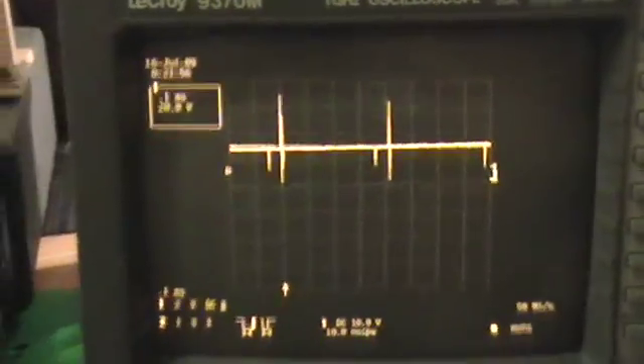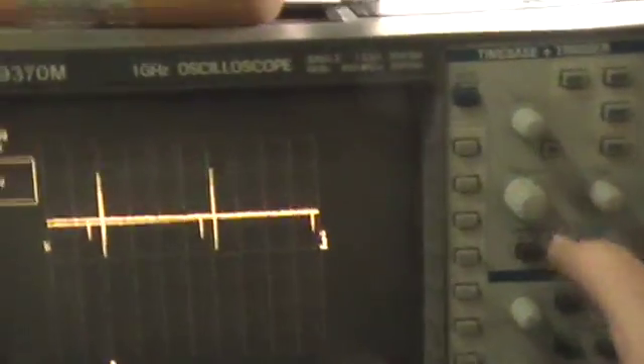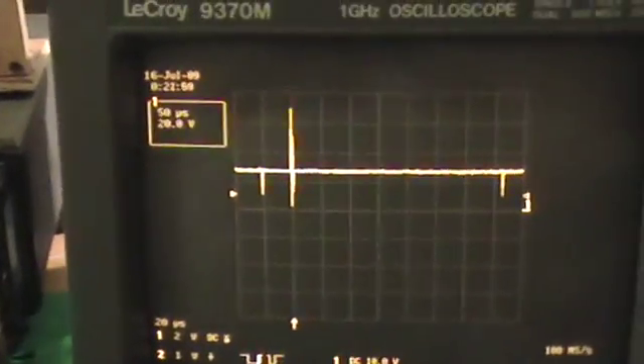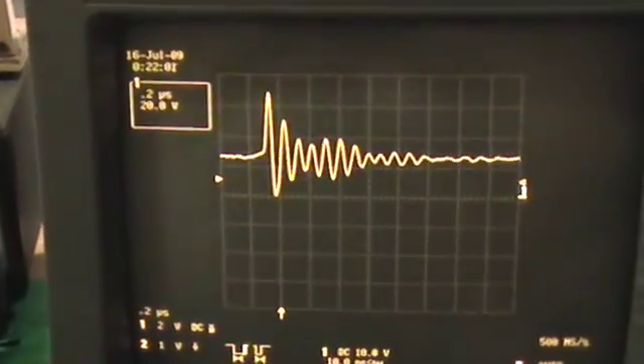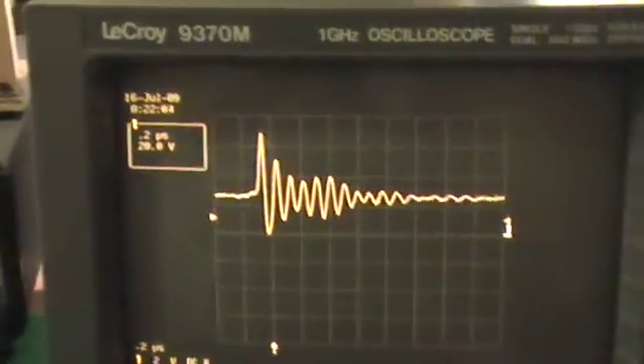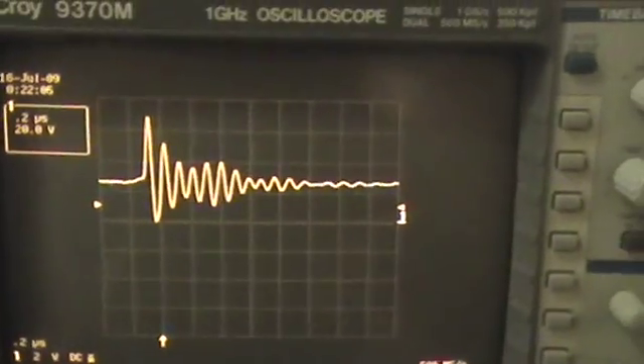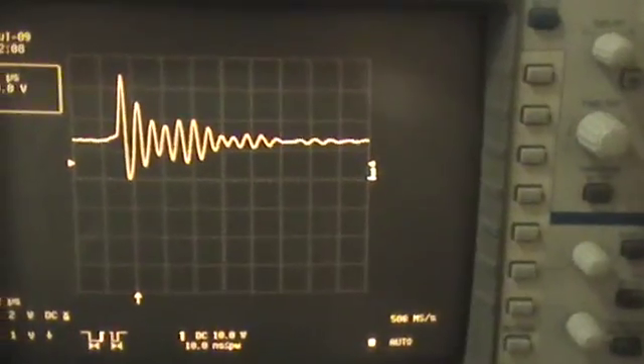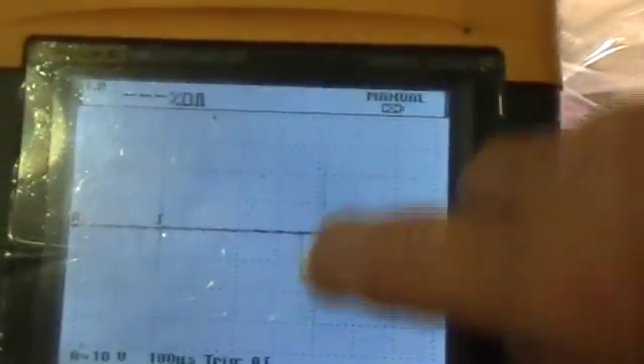Okay, now what I'm going to do now is increase the time base. Actually, let's do it on the LeCroy first, okay. So what I'm going to do now is change the times per division so that we can get and see that inductive ring down at the second, or the trailing edge of that spike. You see that? That's a nice inductive ring down. Now we'll go up and do the same thing for the Fluke. We're going to look at this portion of that spike, okay.